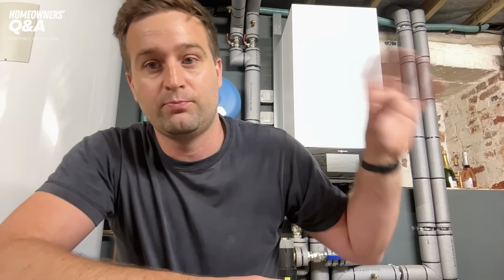What you might find is because you've got so much 10 mil and the resistance for that section is so high, you've almost eaten up the residual head of your pump. Then you might be into the realms of it needing another pump, so you have your primary pump into a buffer, then another pump. Not where you want to go, I would suggest. Really, your first port of call is open loop, and hopefully that one pump can get the flow through those pipes. If it can't, you've got two options really. You've got to add pump power, or you've got to repipe that radiator. It's mathematics, it's physics, it's getting flow down pipes. So it's got to be worked out.